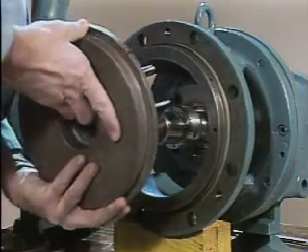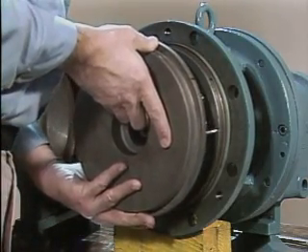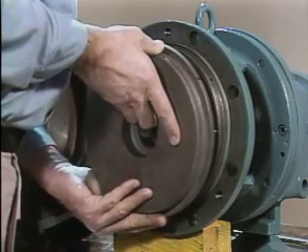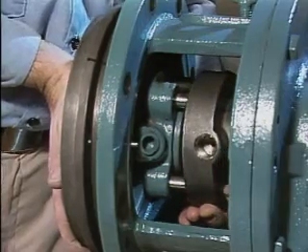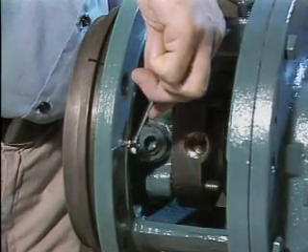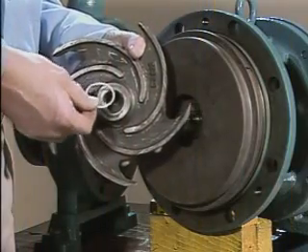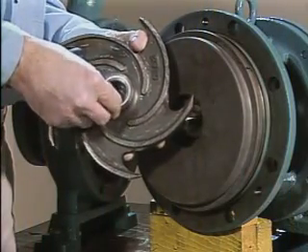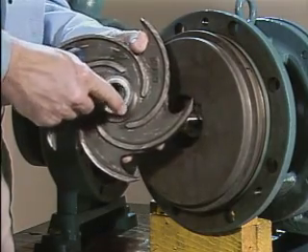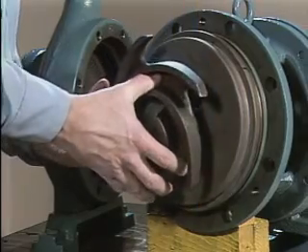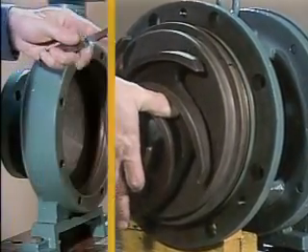Next, the back plate, which includes the stuffing box, is placed onto the frame. The back plate should be properly aligned with the frame match marks, and the stuffing box stud should align with the gland plate. Then the nuts that hold the back plate in place are tightened. Now the impeller can be readied for installation. On this pump, a small gasket is used to seal between the impeller and the shaft sleeve. Once the new gasket is in place, the impeller can be installed.